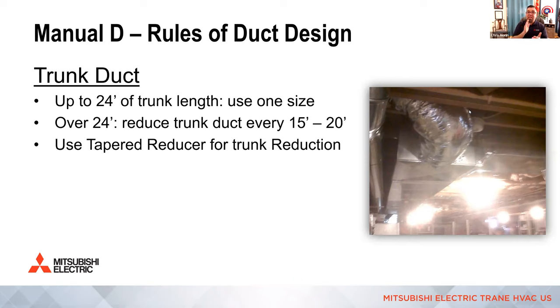Every time you downsize that trunk, you want to have a taper in the trunk. Please don't just put an end cap and stab into that smaller end cap. That is a huge velocity and pressure loss, so that wouldn't meet the rules of duct design. What's going to happen is you're going to depressurize and not get the air. There's going to be a lot of turbulence on the large size, and you're going to get airflow there. But anything past that end cap, where you stab into it for the next run, is going to have very low volume of air and very low velocity because of that turbulence. So a long taper is what you want to use. All right, so those are three.